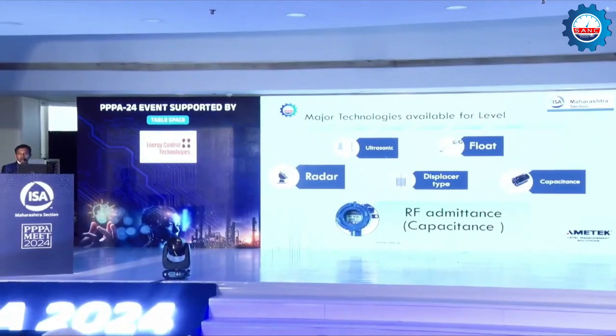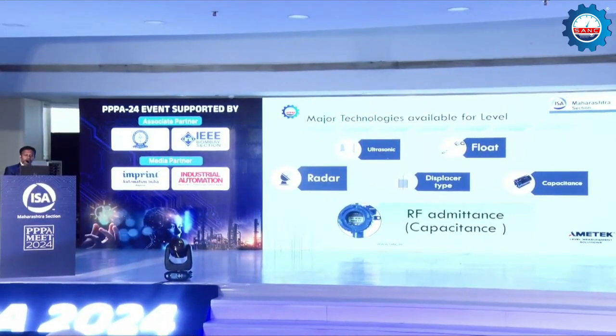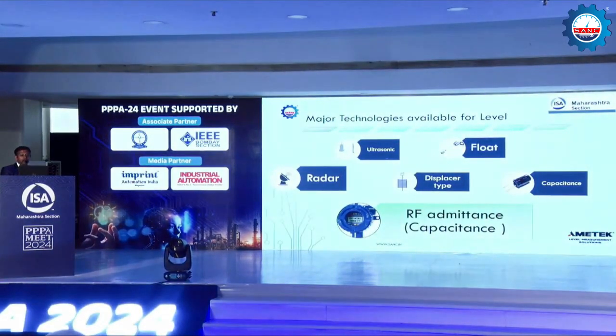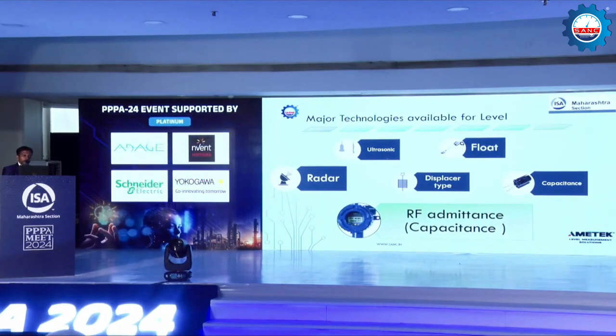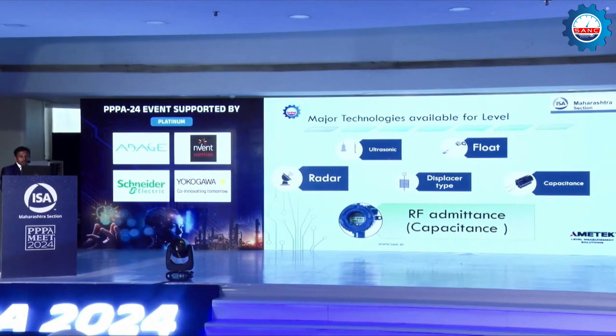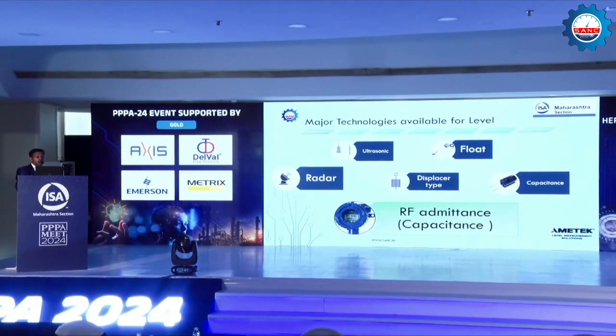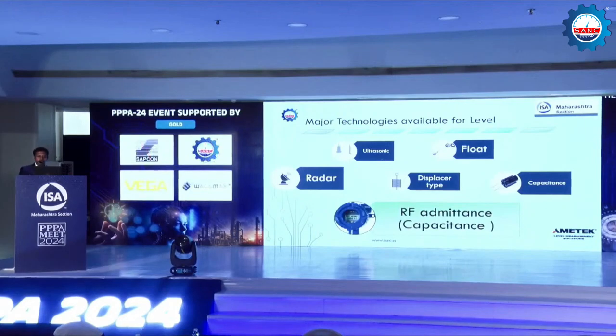Currently, the major technologies available for level measurement are radar, ultrasonic, displacer type, float, and capacitance. We call our product RF admittance, which is eventually a capacitance measurement, but we call it RF admittance, and I'll explain later why. As we all know, radar technologies are common right now, and in many applications we use radar because it is non-contact in nature and very good at level measurement.